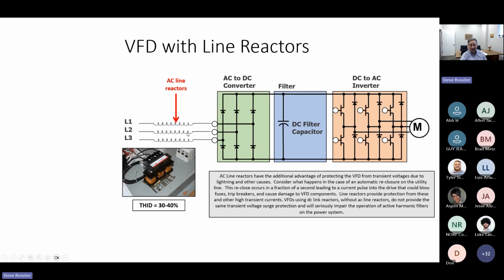It's very, very simple, and we have thousands of line reactors in stock, and they're typically used in variable frequency drives. You can apply them at any impedance level. You can apply them in creating filters, lots of things can be done. And lots of drives have either a DC reactor or an AC reactor as standard. The only problem with that, and it's a good idea, but when you put it inside the drive, there's a pressure to optimize the size of the drive or the amount of impedance used. So we tend to like to put our reactors in the system outside the drive and have the most compact and most elegant drive technology, but some have it inside, and that helps. You can get down to 30 to 40% very easily from that 100% number just by adding a line reactor.